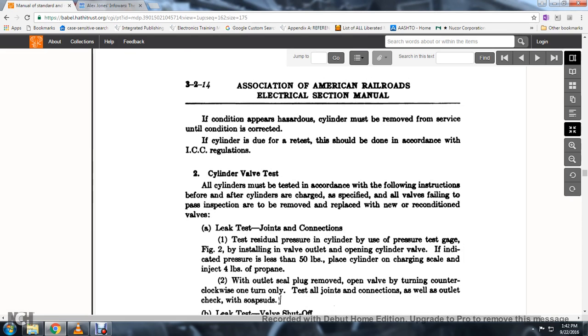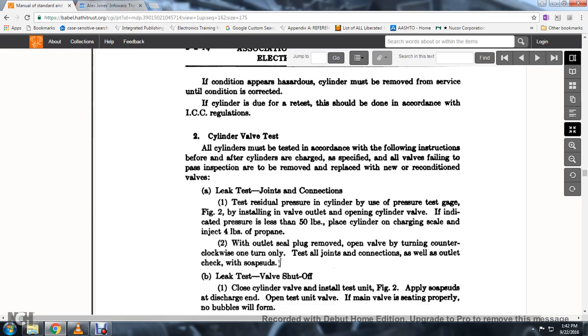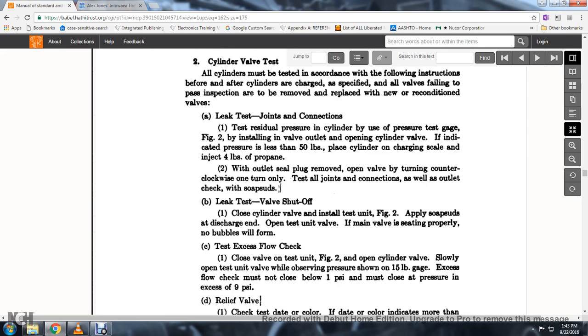Cylinder valve tests: all cylinders must be tested in accordance with the following instructions before and after the cylinders are recharged; all valves failing to pass inspection must be removed and replaced with a new or reconditioned valve. Leak test joint connections: install the test pressure gauge figure 2 in the valve outlet opening. If the indicated pressure is less than 50 pounds, place the cylinder on a charging scale and inject 4 pounds of propane with the outlet seal plug removed; open the valve one turn counterclockwise only, then test all joint connections and the outlet check with soap suds.